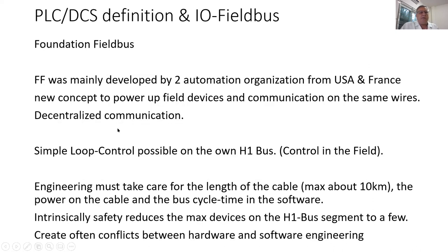Foundation Fieldbus is a bit more complicated because they brought in a new idea, especially for the petrochemical industry, for pipelines and so on, where they have maybe some pump stations or any valve somewhere in the desert, I don't know, where they have the pipes running. And they need to bring power also. We don't want to get only the data, we have to supply our devices with power. And that is the new concept here, that we bring the power on the same wire with the data. So there's some electronics to separate this later, but on the other hand, it produces some more problems, and of course, that is also limited.